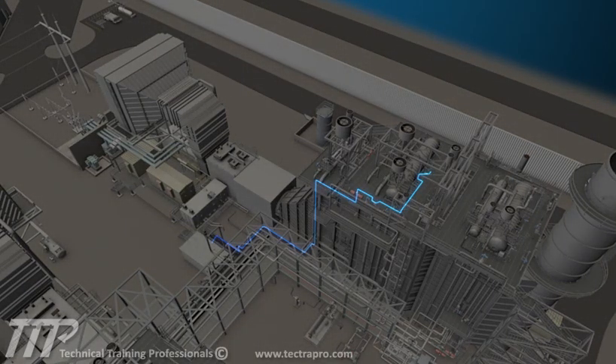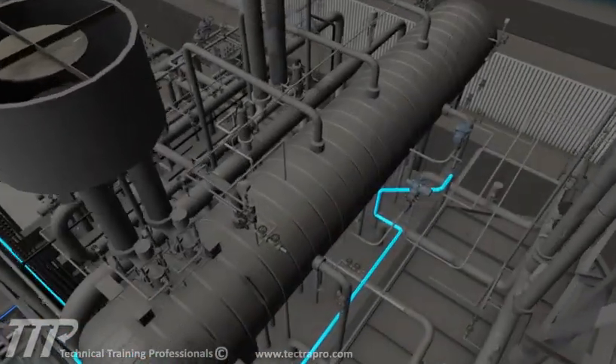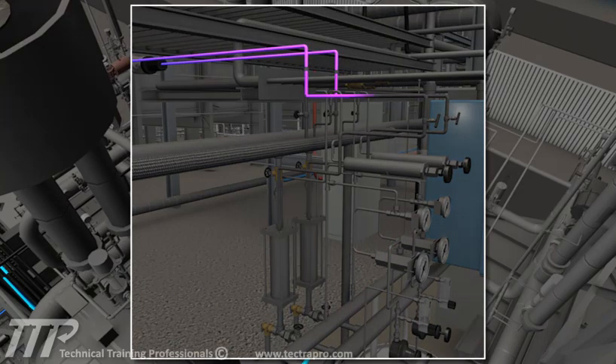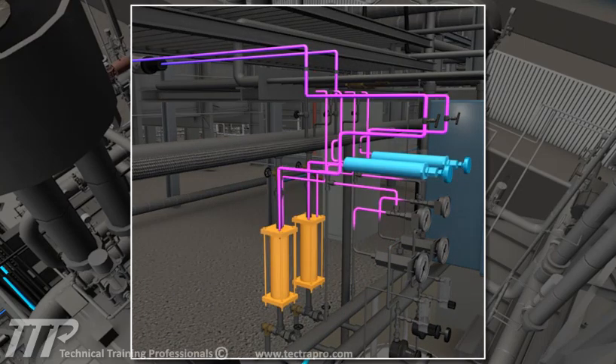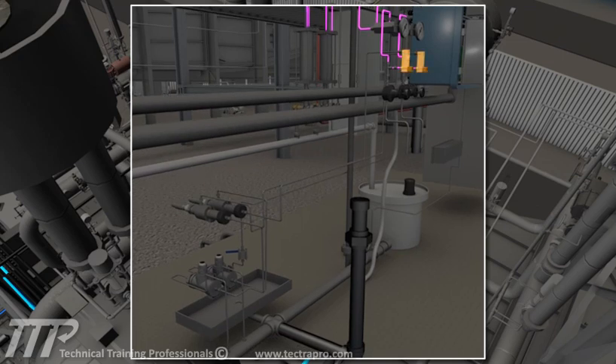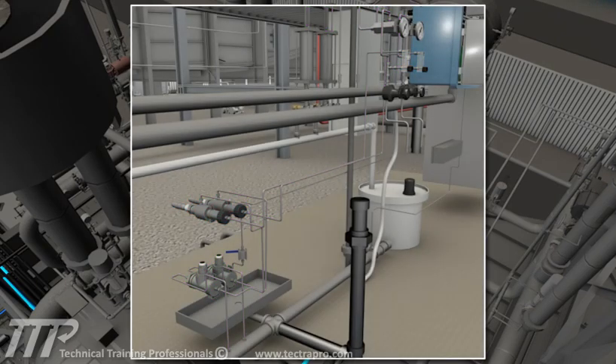Sample points 12 and 13 are the high-pressure drum boiler water section from HRSG 1 and 2. At the sample panel, the high-pressure drum boiler water is cooled and its pressure is adjusted. Flow is adjusted before entering the pH analyzer and the specific conductivity analyzer. Provisions for manual sampling are available to further analyze the conditions of the water.